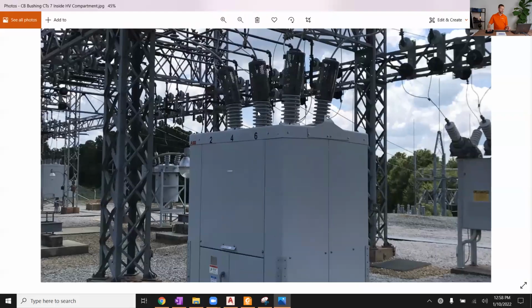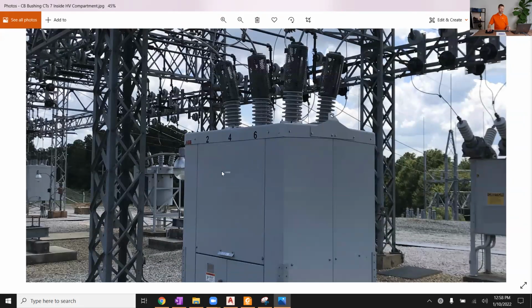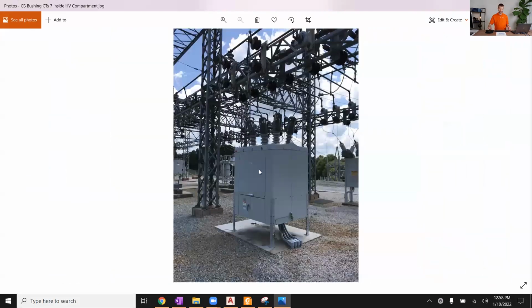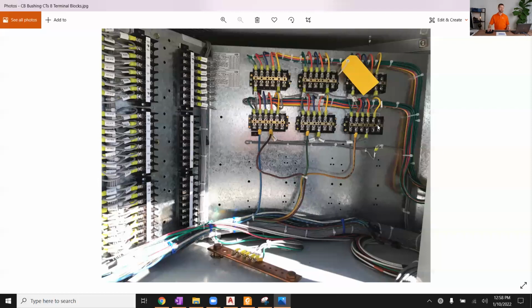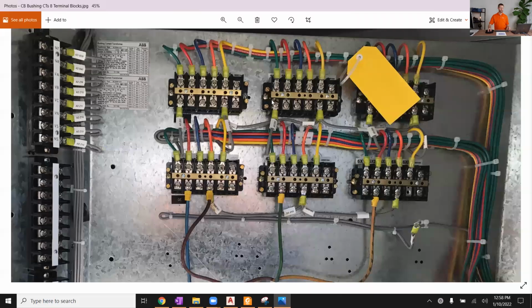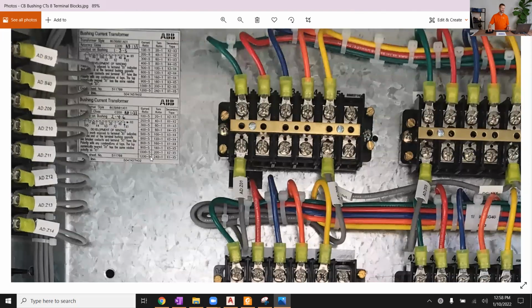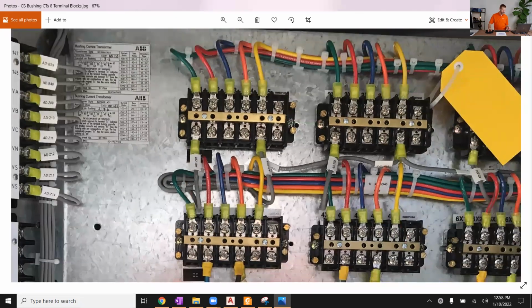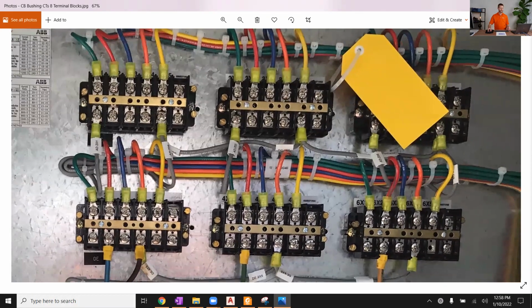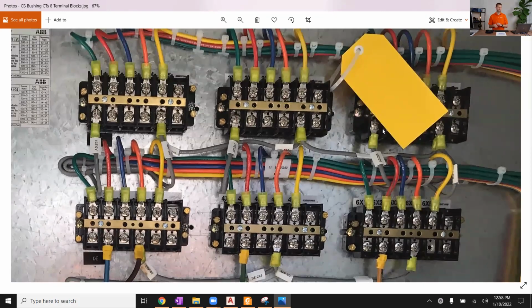This is an ABB RMAG. You notice here you don't see bushing CTs up here. They're actually buried inside of this high voltage compartment in the enclosure cabinet. But there are bushing CTs in here, even though you don't see them as explicitly. And if you look down in your breaker cabinet, you'll see these different bushing CT terminal blocks. You'll see the bushing CT nameplates, again, the 1200:5 at full tap. So you'll see the 135 and the 246 bushing CTs. This breaker has 1 CT per bushing, and looks like full tap X1 to X5 on the 135 side, but it looks like tapped down to X2 to X4 on the other bushing. That was a bus differential relay application that had to work with some old electromechanical relays.